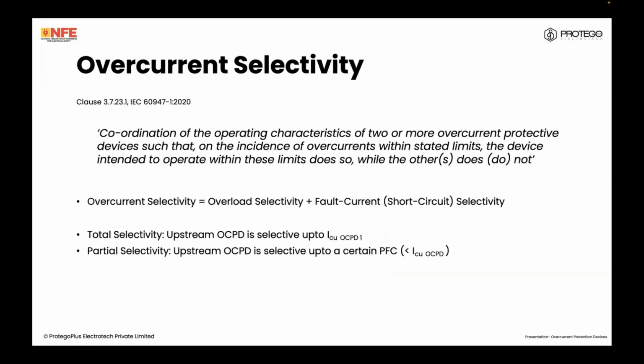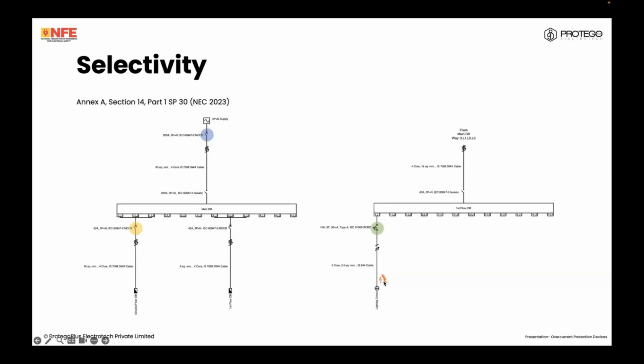Overcurrent selectivity, as defined by clause 3.7.23.1 in IEC 60947-1 2020, is the coordination of the operating characteristics of two or more overcurrent protective devices such that, in the incidence of overcurrents within a given limit, one device is intended to operate within these limits, while the other, which is the upstream breaker, does not do so. So if I go back here, if a fault is here, only this RCBO should disconnect. This MCCB should not disconnect, and this MCCB definitely should not disconnect. Or if this distribution circuit has a fault, only this distribution circuit should lose power, not the circuit breaker that protects the entire supply to the installation.